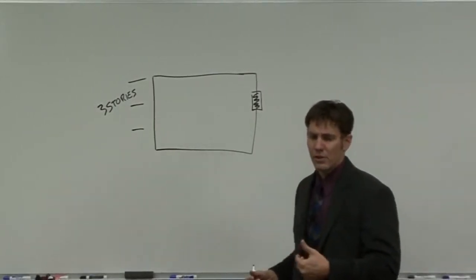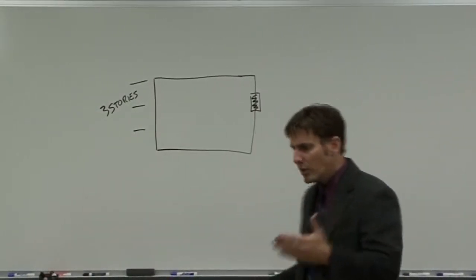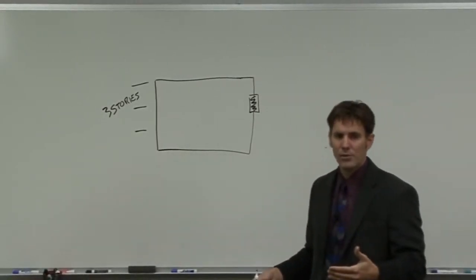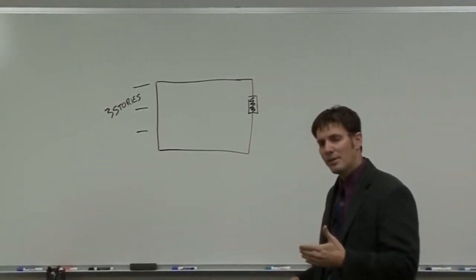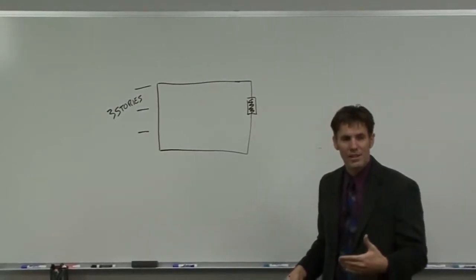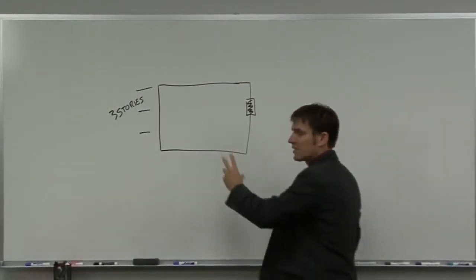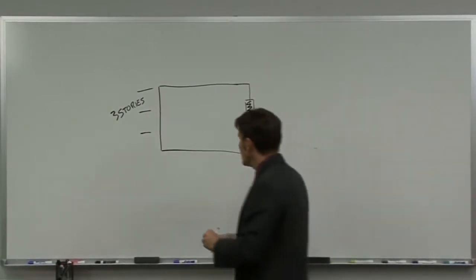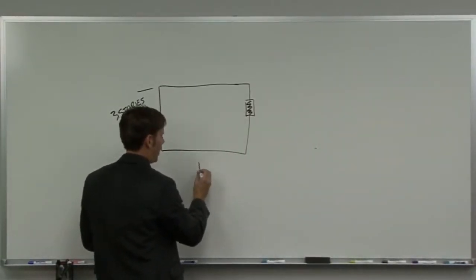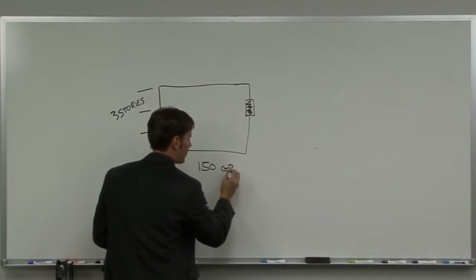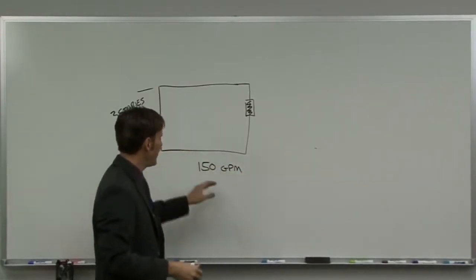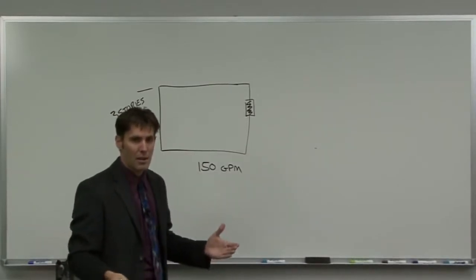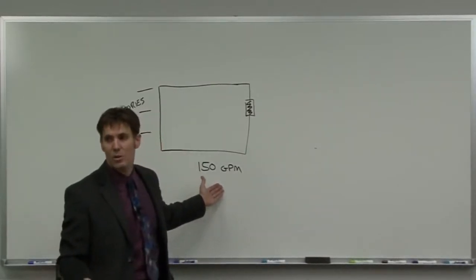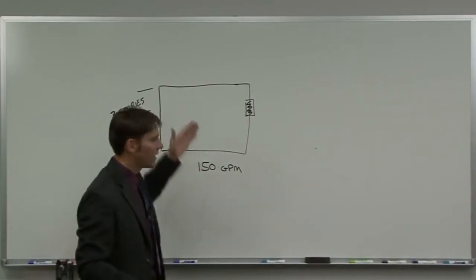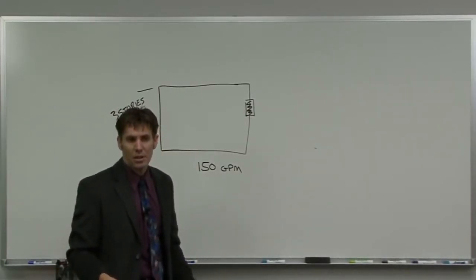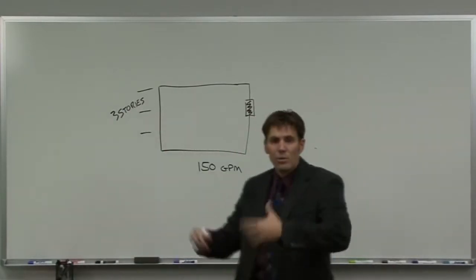Too many HVAC professionals that I've worked with have told me, well, we use centrifugal pumps because centrifugal pumps move water. Now, I'm here to tell you that's not what happens, and we're going to go over the basics. A pump is not put in this system to give you a flow rate. Let's say in this system, I needed a flow rate of 150 gallons per minute, GPM. If I want 150 gallons per minute, I put a pump in to do that. But that pump is extremely stupid. It's got no intelligence. It's not going to say, okay, give me 150 gallons per minute. All it's going to do is rotate.